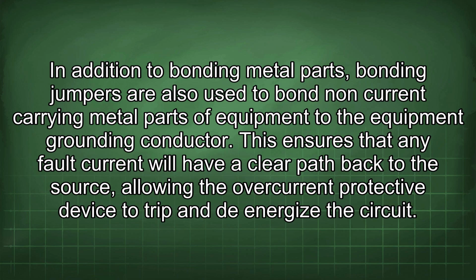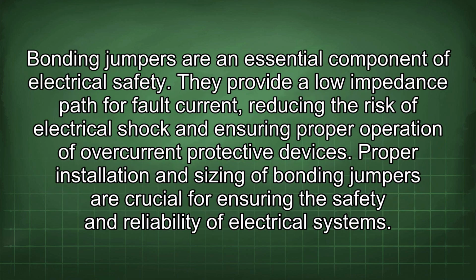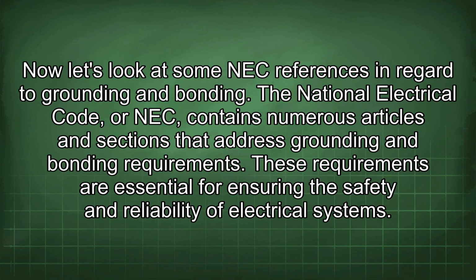To avoid ground loops, it's important to bond all metal parts to a common grounding point. In addition to bonding metal parts, bonding jumpers are also used to bond non-current carrying metal parts of equipment to the equipment grounding conductor. This ensures that any fault current will have a clear path back to the source, allowing the overcurrent protective device to trip and de-energize the circuit. Bonding jumpers are an essential component of electrical safety. They provide a low impedance path for fault current, reducing the risk of electrical shock and ensuring proper operation of overcurrent protective devices. Proper installation and sizing of bonding jumpers are crucial for ensuring the safety and reliability of electrical systems. Now let's look at some NEC references in regard to grounding and bonding.